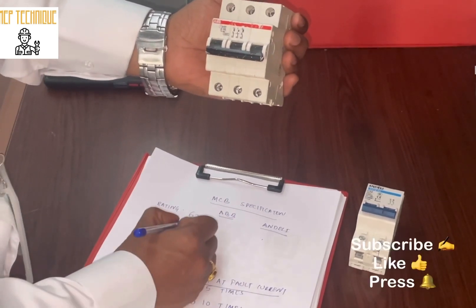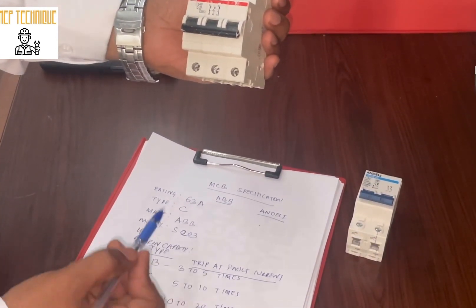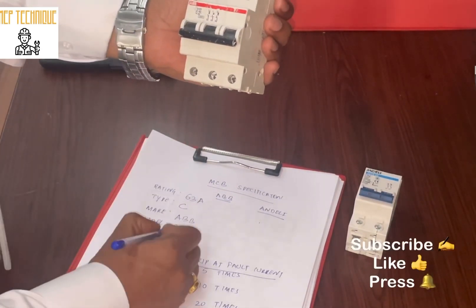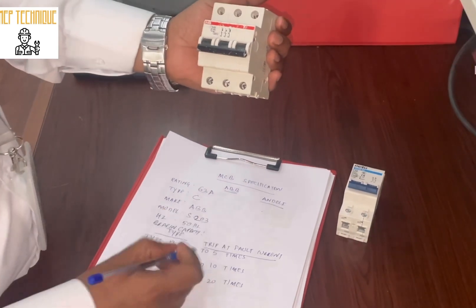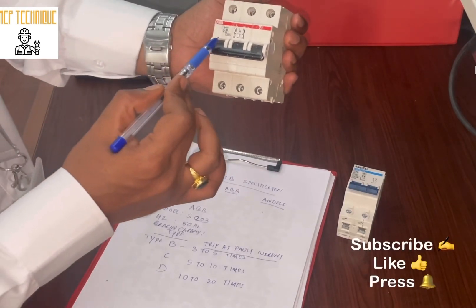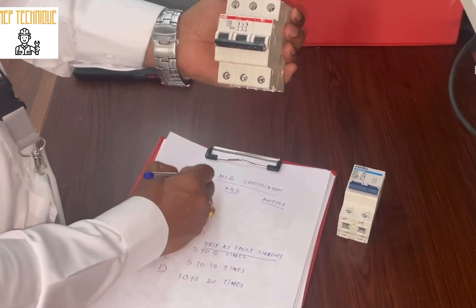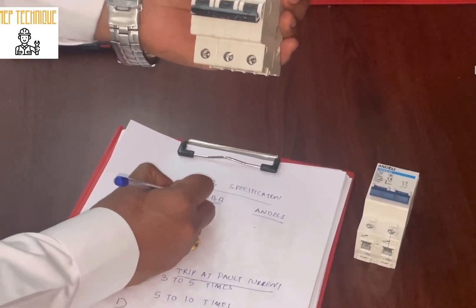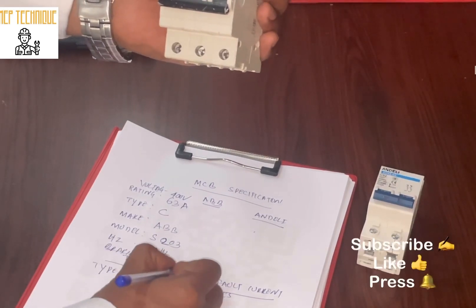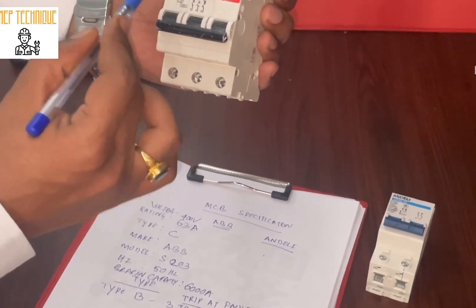The rating is C63, that means this is a 63 ampere, C-class breaker. The frequency is AC, so this MCB is applicable for AC at 50 Hz. There is also mentioned 400V and 6000 - that means the voltage is 400V and 6000 is the breaking capacity of the breaker.